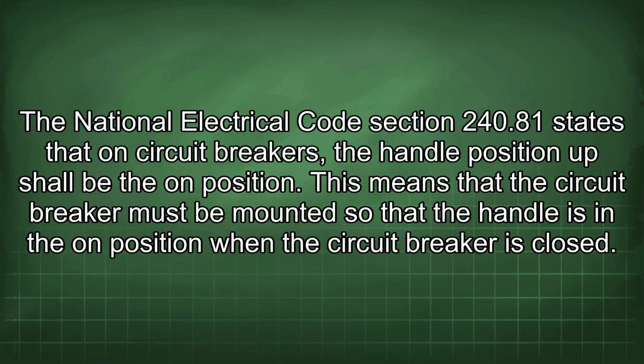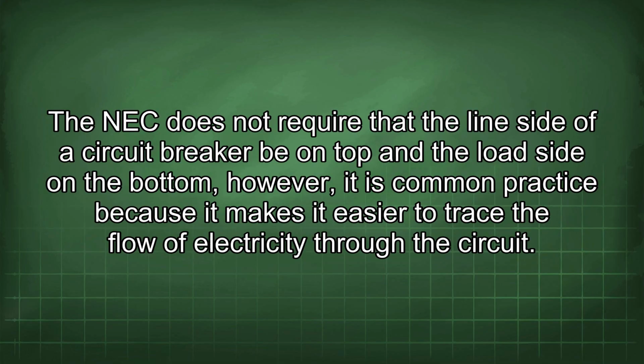The National Electrical Code Section 240.81 states that on circuit breakers the handle position up shall be the on position. This means that the circuit breaker must be mounted so that the handle is in the on position when the circuit breaker is closed. The NEC does not require that the line side of a circuit breaker be on top and the load side in the bottom. However, it is common practice because it makes it easier to trace the flow of electricity through the circuit.